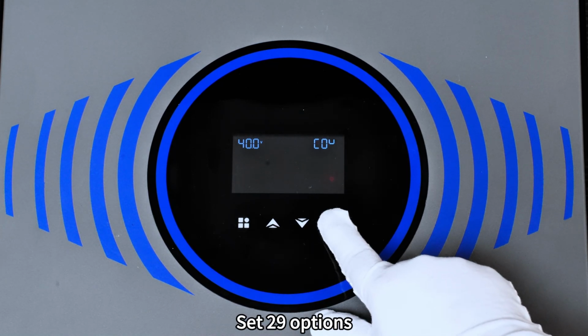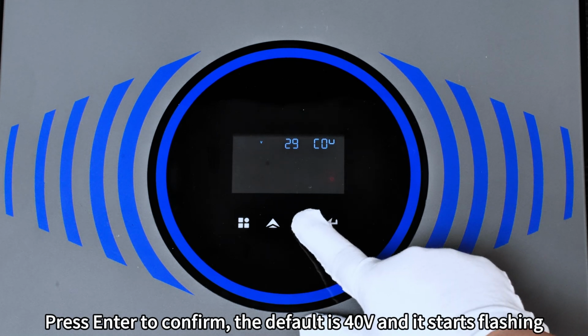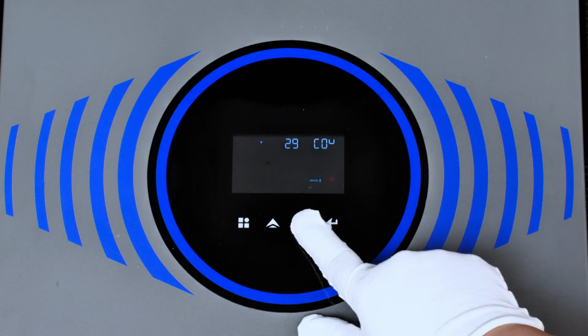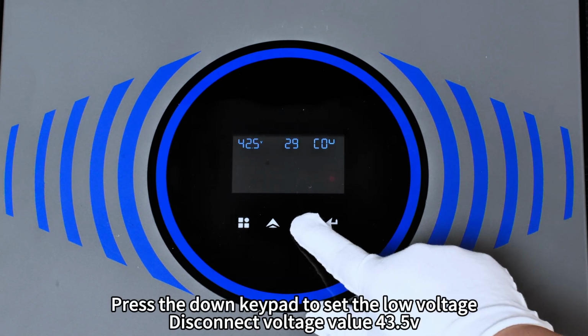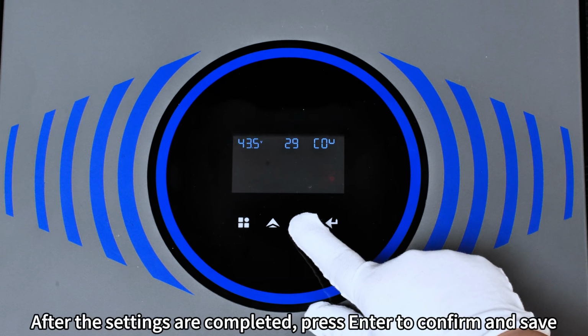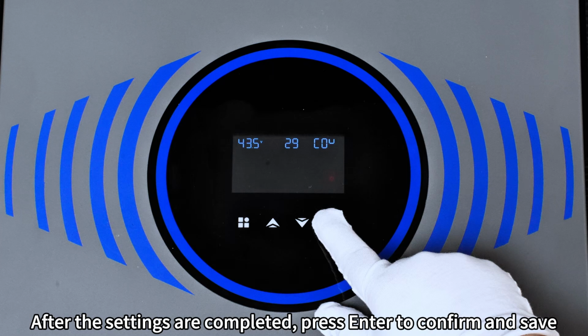Next, settings option 29. Press Enter to confirm. The default is 40 V and it starts flashing. Press the down key to set the low voltage. Set the disconnect voltage value to 43.5. After the settings are completed, press Enter to confirm and save.